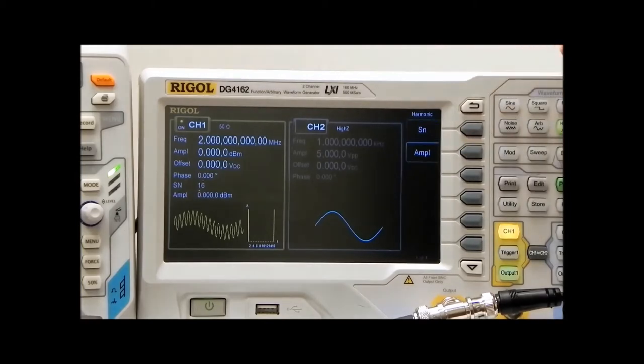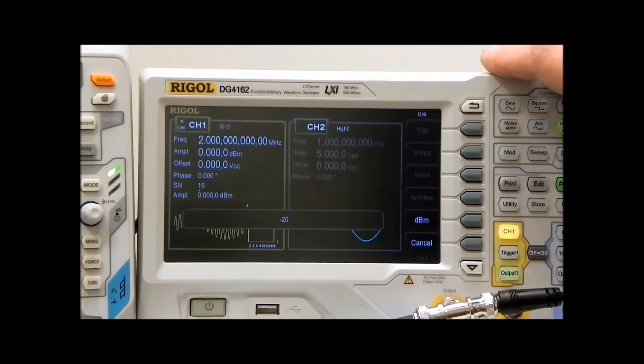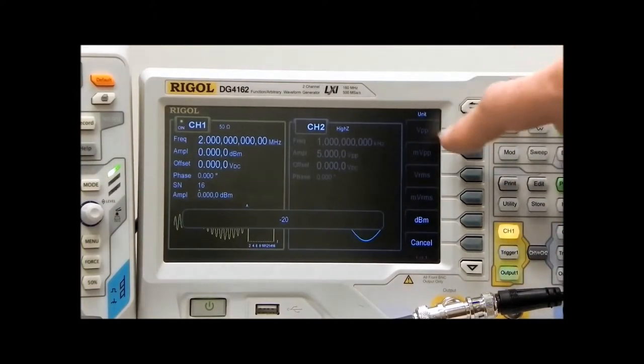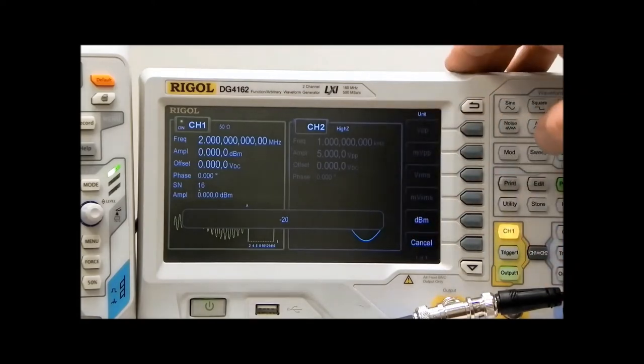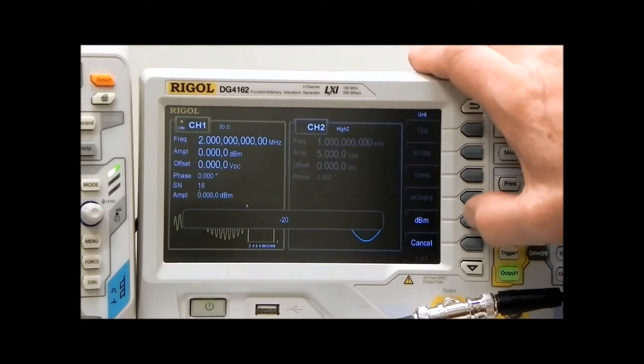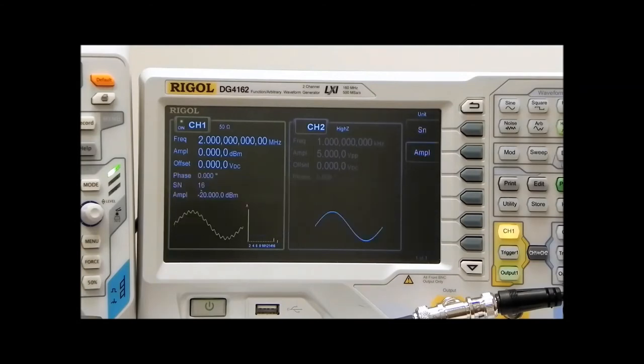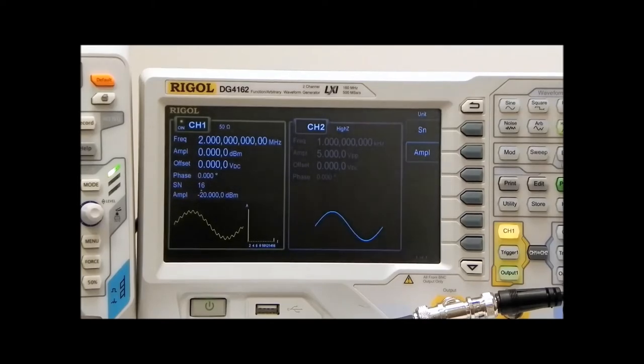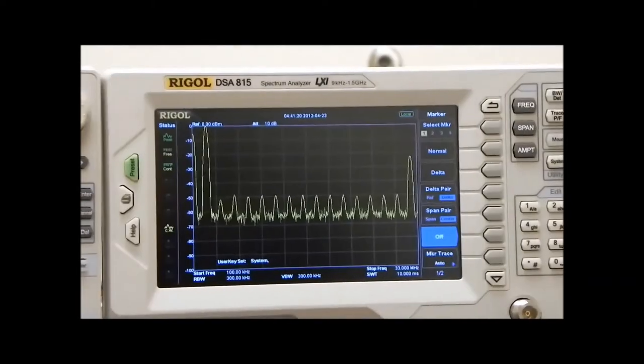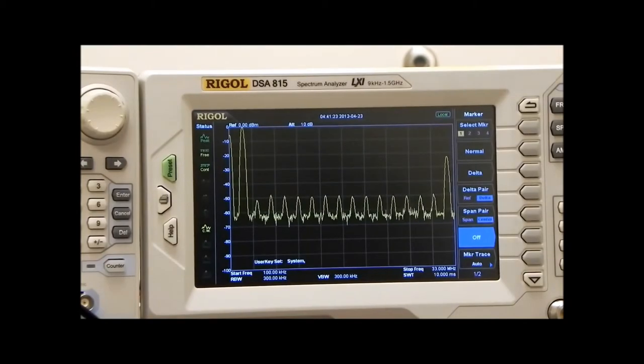What I'm going to do now is I'm going to drop it by 20 dB. And that should be large enough that it will show up easily on the spectrum analyzer. I can set it to a number of different levels in this particular demonstration. I've set it to express itself in dBm. And so by waiting for the waveform, you'll see that it indicates that it's not going to have very much signal, or it's quite a bit reduced. And indeed, if I look over here, you'll notice that it is down about 20 dB.